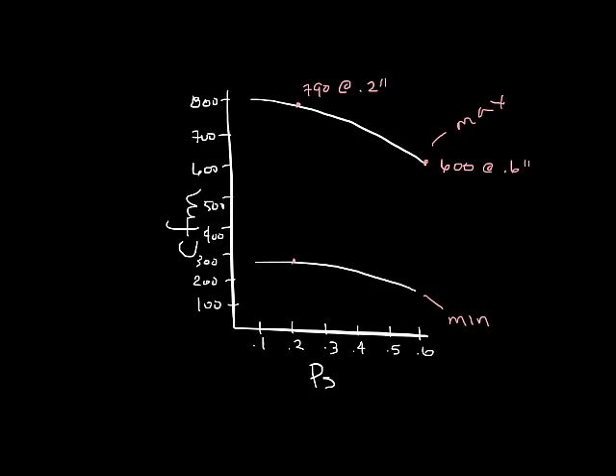Same thing for the minimum line. Down here at 0.2 you have about 250 CFM and at 0.6 inches you have about 175.